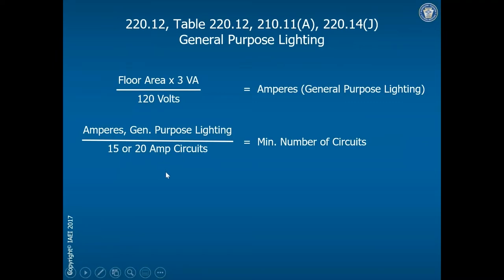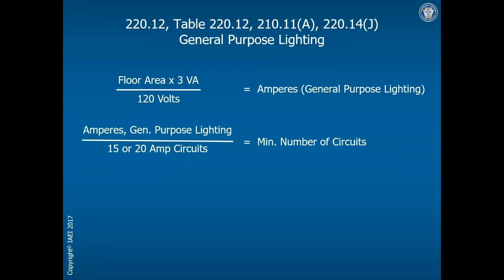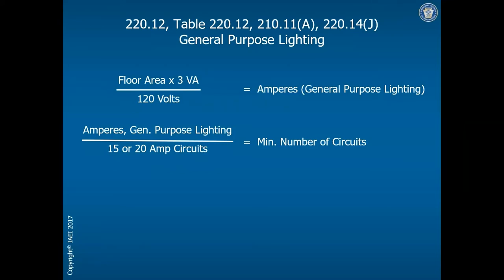I put 15 or 20 amps here because per the National Electrical Code, the minimum size branch circuit for a dwelling unit is 14-gauge copper, protected by a 15-amp breaker. However, some jurisdictions have a local ordinance requiring a minimum of 12-gauge wire even for general lighting circuits. In that case, those circuits would be protected at 20 amps. That's why I listed both 15 and 20 amp options.